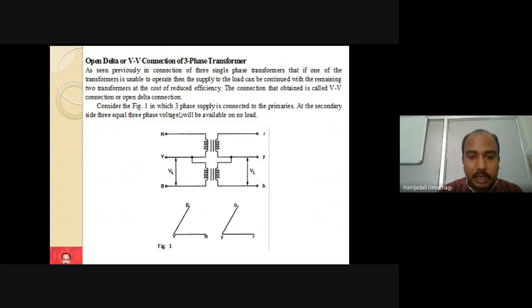Consider the figure 1 in which three-phase supply is connected to the primary. So this is the VV connection diagram. Here the primary is connected to line voltage VL. VL is the voltage that is measured between phase Y and phase B. Okay, that is connected to the primary side. At the secondary side, equal phase voltages will be available on the load side. So here on the load side, that is the secondary side, we are also getting the voltage VL. So the small r, small y, small b are the secondary side phase connections, whereas capital R, capital Y, capital B are the primary side connections.